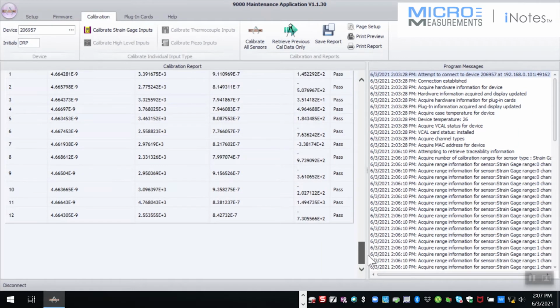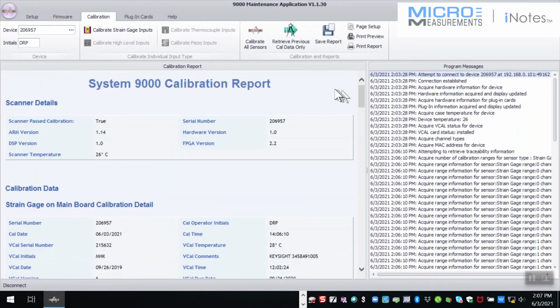One other thing I'd like to point out is when you're running this VCAL card, I recommend that you disconnect your inputs. I have had some customers that went through this calibration and found that a channel, in particular the excitation, had failed, and it had nothing to do with the scanner. It was their input had a path to ground or a short to ground that caused that channel to not be within spec. So this VCAL card provides the voltages. So when you get to this stage, it's a good idea to just disconnect your inputs, run the VCAL. Once it passes like ours has, then you can reconnect those inputs back into the scanner.